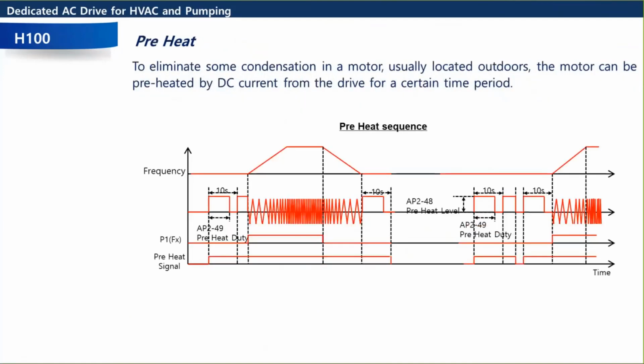This one's useful. I think this is only on the H100, if I remember, which is motor preheat. So motor preheat is a way to eliminate the condensation that can form in a motor. Okay, so if there's a temperature difference inside of the motor versus the outdoors, depending on where the motor is installed, that can cause condensation to form on the motor windings. So then when you start up a motor, you could be getting ground faults or over voltages or weird issues like that caused by the condensation. What motor preheat does is it injects a small amount of DC current from the drive into the motor, and it keeps the windings just warm enough so that no condensation is allowed to form.